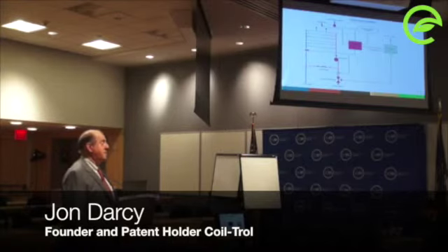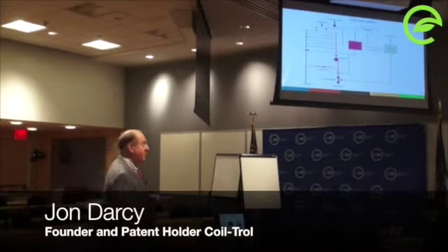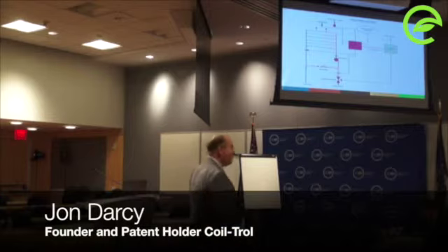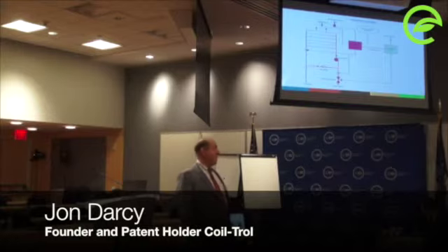If I take a 40% savings on a 250 horsepower pump, that's 100 horsepower, running 3,000 hours a year. Okay, 2,500 hours a year. So it's a big number.